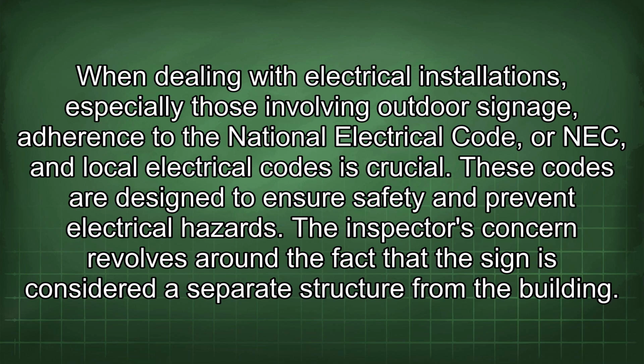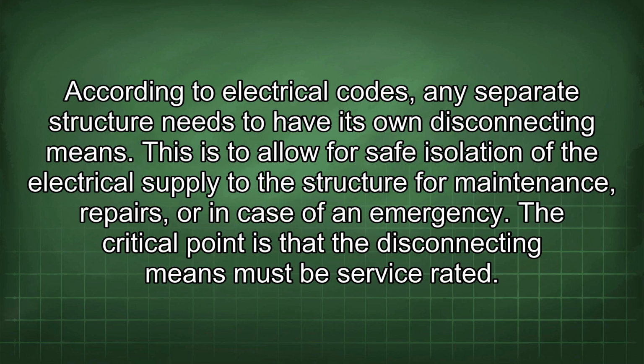When dealing with electrical installations, especially those involving outdoor signage, adherence to the National Electrical Code, or NEC, and local electrical codes is crucial. These codes are designed to ensure safety and prevent electrical hazards. The inspector's concern revolves around the fact that the sign is considered a separate structure from the building. According to electrical codes, any separate structure needs to have its own disconnecting means. This is to allow for safe isolation of the electrical supply to the structure for maintenance, repairs, or in case of an emergency. The critical point is that the disconnecting means must be service rated.